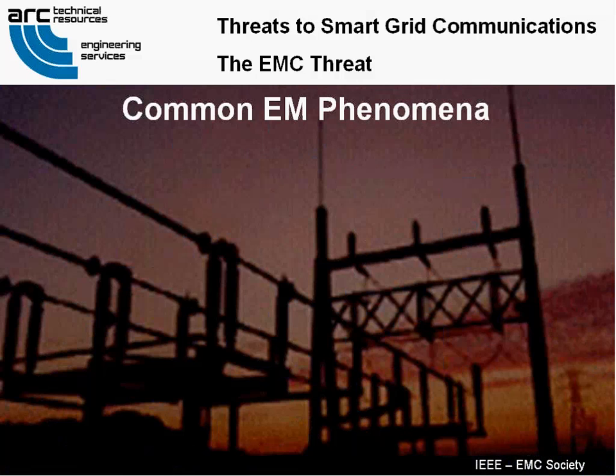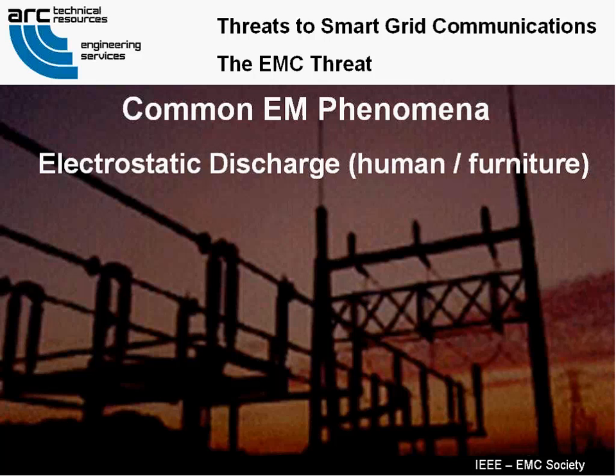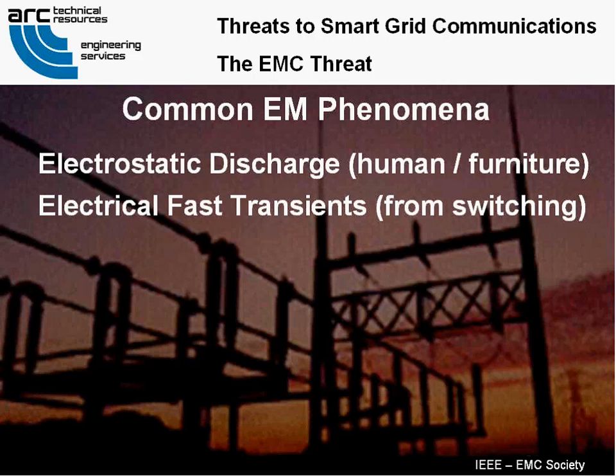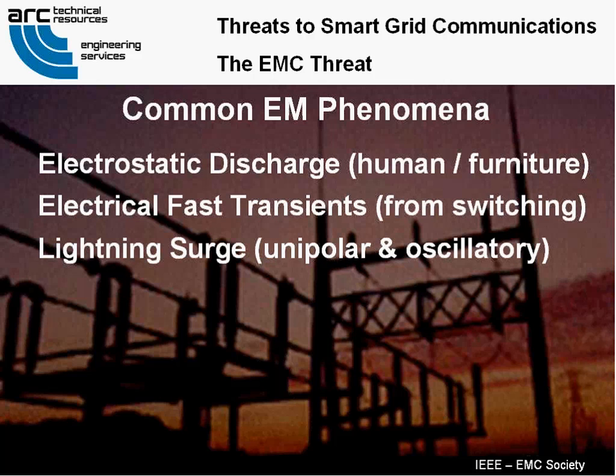Immunity tests simulate common electromagnetic phenomena that could cause upset. One familiar phenomenon is electrostatic discharge, or ESD, from human or furniture contact with vulnerable equipment. Another is electrical fast transients from switching operations with contact bounce and arcing. These fast rise time, low energy events are common in utility settings and readily latch up digital electronics not designed to resist their intrusion. Lightning strikes or switching events cause electrical surges measuring into the thousands of amps.